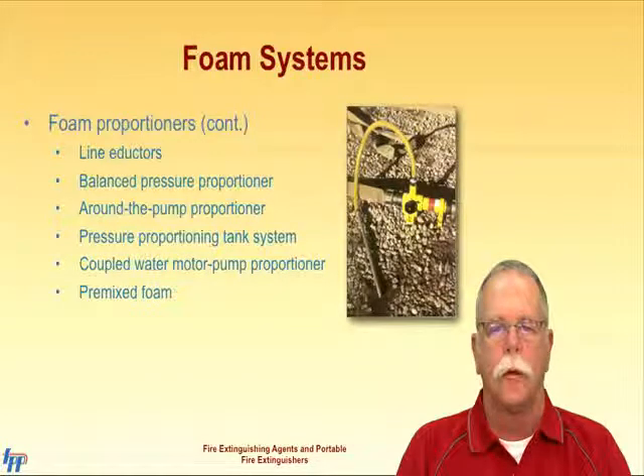Foam proportioners work on one of 2 principles. Foam is picked up when water rushes through the eductor, creating a Venturi effect, or foam concentrate is injected into the system stream under pressure. Line eductors use water moving through them to create a Venturi effect, drafting the foam from the container into the stream of water. Balanced pressure proportioners allow foam concentrate to be put into different lines at different rates, or not at all, allowing cooling lines and foam lines to run simultaneously.